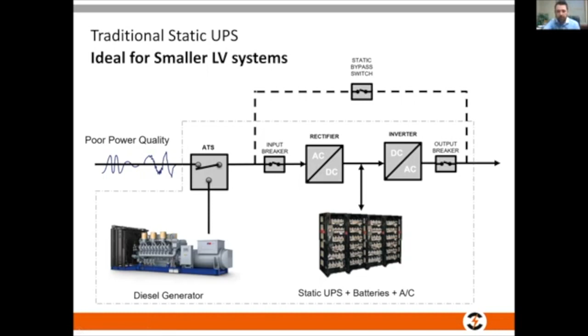If you agree with that high-level idea, then you also agree that the batteries are pretty much supplying a transition of power from the utility failing or being poor power quality over to the diesel generator. The diesel generator provides long-term support to your critical load, typically within 10 seconds, maybe longer. In that instance, providing the alternator spins at 1800 RPM, you're okay, because once the diesel generator stabilizes, it's at 1800 RPM, a standard 4-pole machine at 60 hertz, or 1500 RPM for 50 hertz machines. Once the alternator is at 1800 RPM and the engine has stabilized, the clutch closes. Now, in a diesel rotary UPS, we're slightly different.